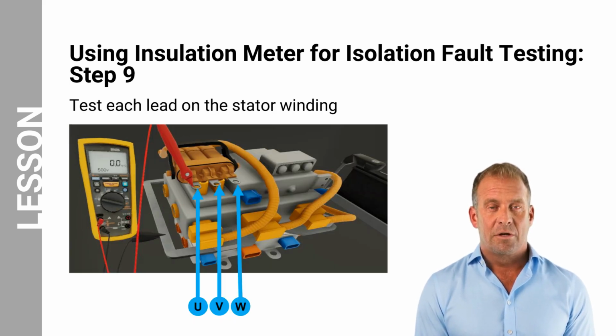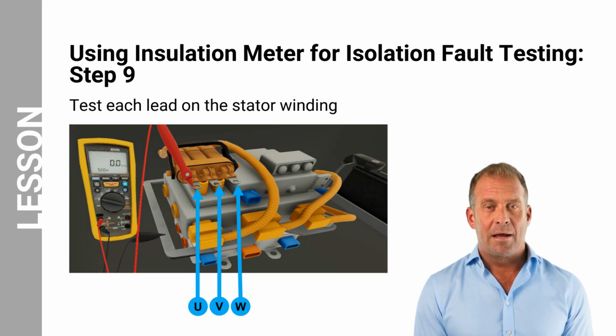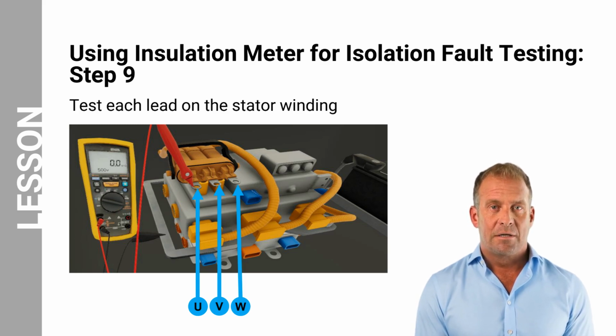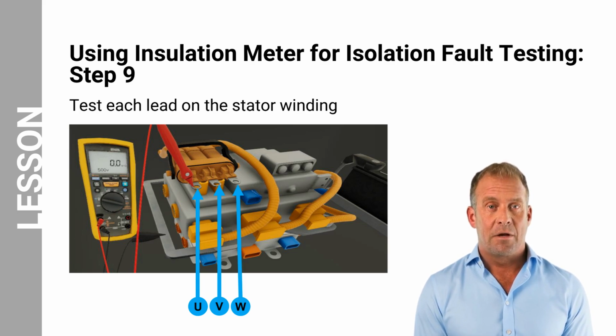Step 9. Use your insulation meter to test each lead. By performing this action, you apply high voltage and low current from the positive test lead to the stator winding, and attach the negative test lead to the motor housing or an available chassis component. Hold either test button for 3 seconds to test the first lead. The meter reading should be infinite. As an example, in this lesson, the meter reading is displayed as 550 megaohms. As displayed on your screen, this process must be repeated for all connections U, V, and W.